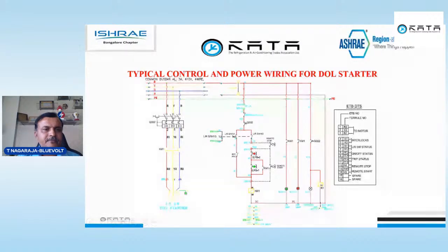Three-phase RYB will come. This MPCB has both thermal and magnetic trips, so you can set the thermal range. If the current crosses your set point, it will take 60 to 90 seconds and it will trip. So there is no need to use one more overload relay. Nowadays, MPCBs are also coming with only short circuit protection, and along with that we can use an overload relay.